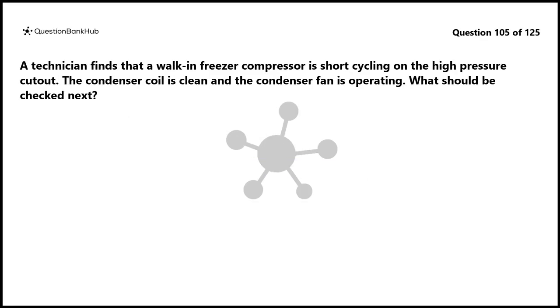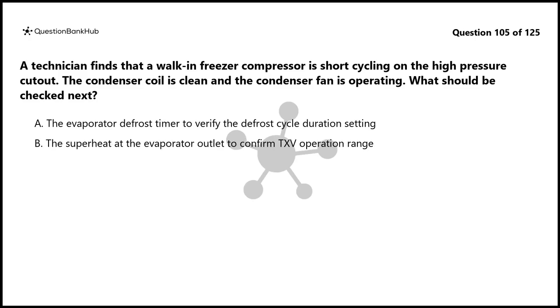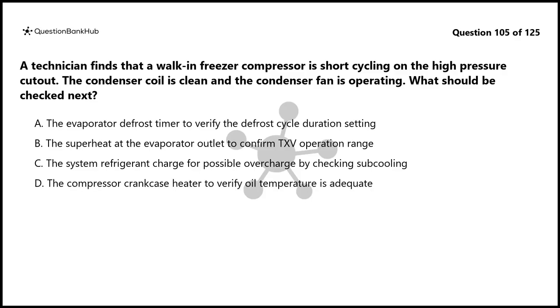Question 105. A technician finds that a walk-in freezer compressor is short-cycling on the high-pressure cutout. The condenser coil is clean and the condenser fan is operating. What should be checked next? A. The evaporator defrost timer to verify the defrost cycle duration setting. B. The superheat at the evaporator outlet to confirm TXV operation range. C. The system refrigerant charge for possible overcharge by checking subcooling. D. The compressor crankcase heater to verify oil temperature is adequate.